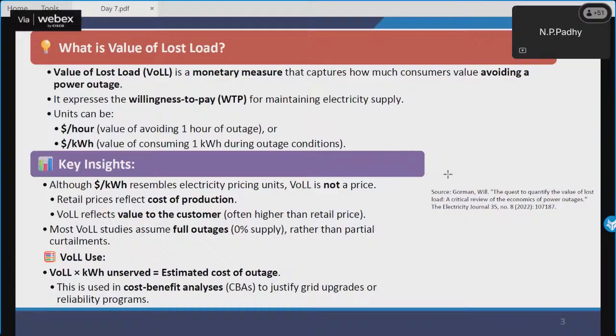Although dollar per kilowatt hour resembles electricity pricing units, VOLL is not a price. Retail prices reflect cost of production. VOLL reflects value to the consumer, often higher than the retail price, which is true. Most VOLL studies assume full outages, 0% supply, rather than partial curtailments. So VOLL times kilowatt hour unserved equals estimated cost of outage. This is used in cost benefit analysis, CBA, to justify grid upgrades or reliability programs.